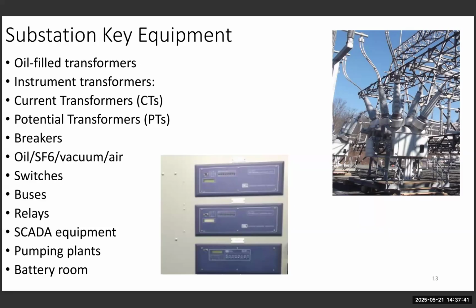So if the battery is dead and a fault happened, we will not be able to open the breaker to isolate the issue. I had this once in my career. The battery was dead. The alarm didn't work for whatever reason, and the whole station basically burnt because there was a failure. The failure was not detected.